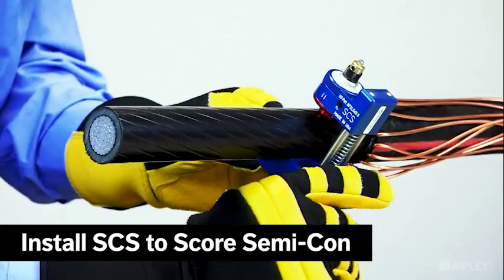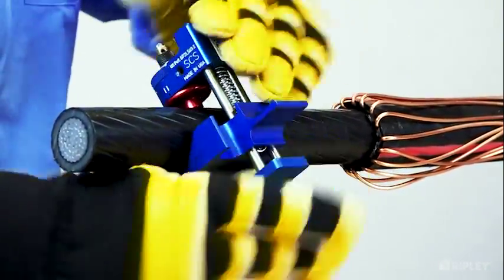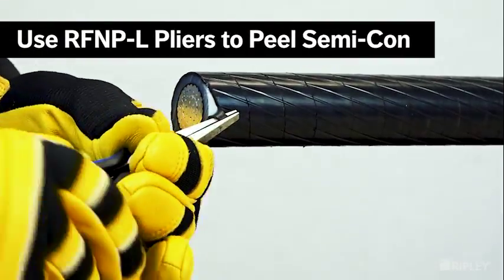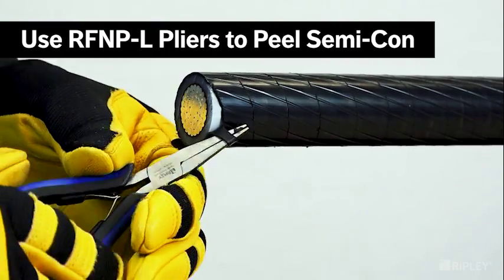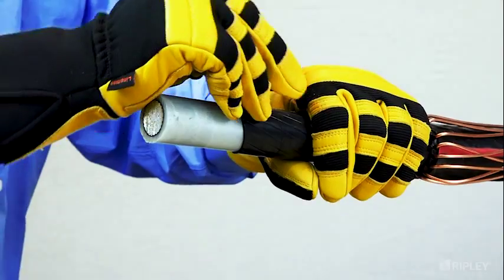Install a semi-con scoring tool, such as the SCS, onto the cable to score the semi-con layer. Use a pair of flat-nose pliers, such as the RFNP-L, to begin peeling away the semi-con and exposing the insulation.